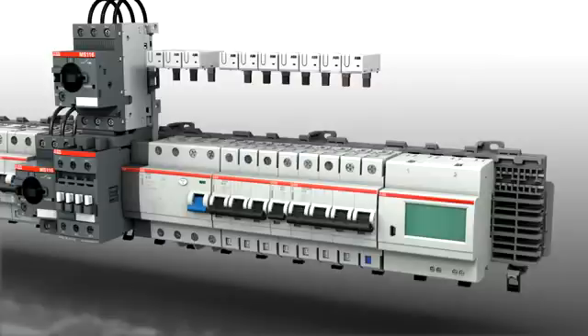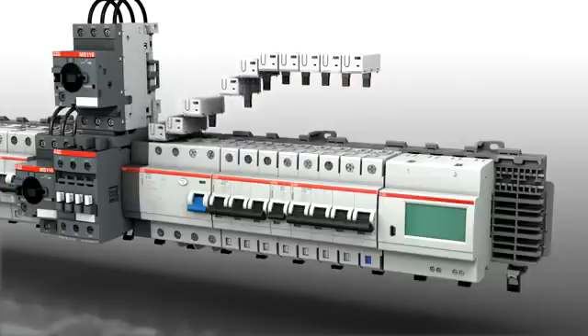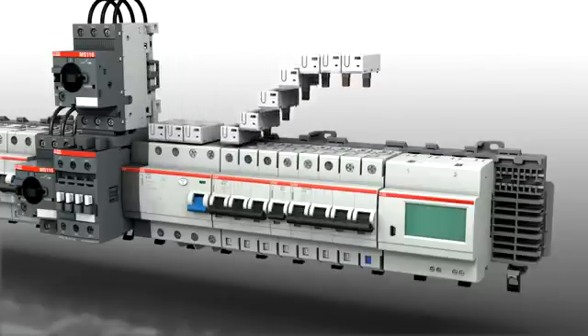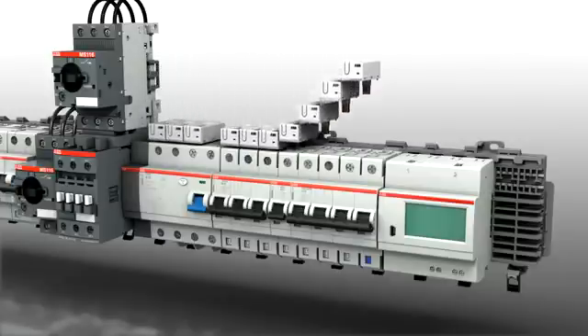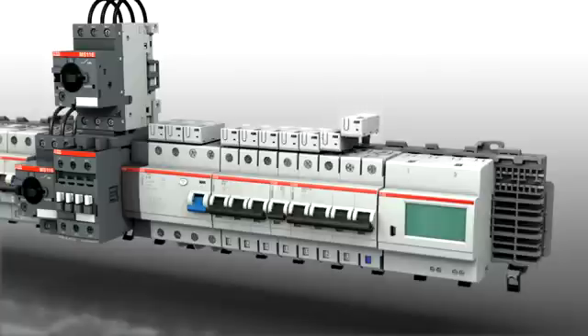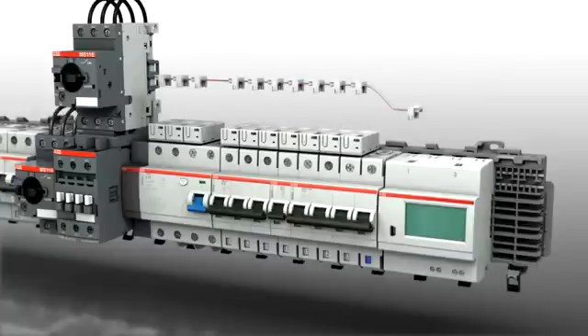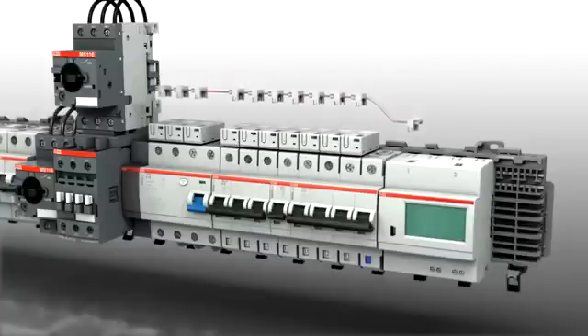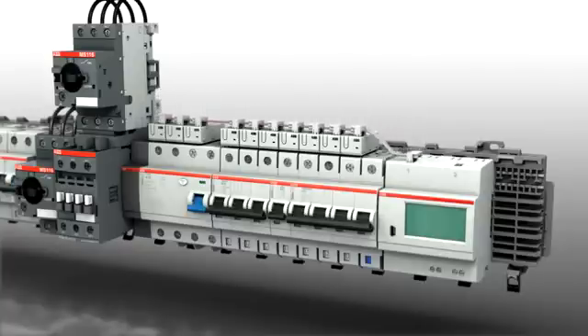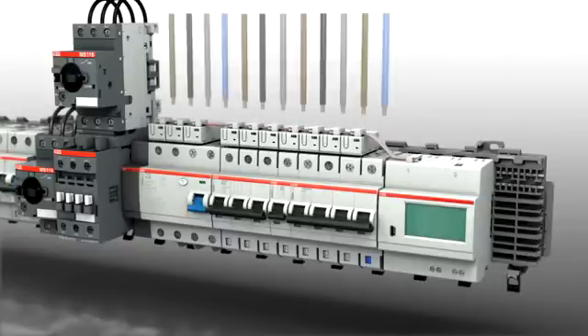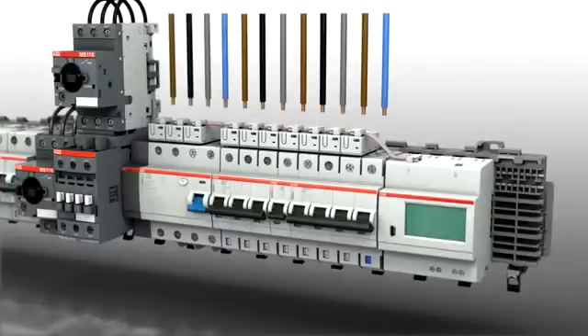A current measuring module can be fitted to the output terminals of the devices. This can be used to measure the current per output. The modules are connected to each other via a bus system. This enables overloads to be detected and possible failures prevented.